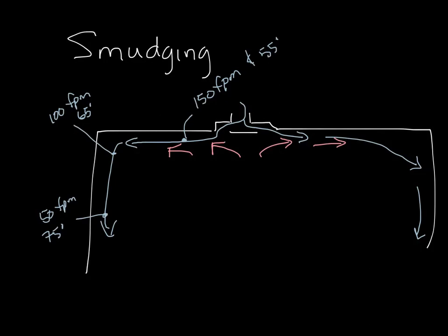The room air is being mixed in with the supply jet to slow the jet down and warm the air up. Since the room air is not filtered, it can carry dust particles to the ceiling, probably not as big as this, but you get the point. And the dirt will stick to the ceiling tiles. Where it is on the tiles depends on the airflow pattern of the diffuser and where the Coanda pocket is. Remember that the Coanda pocket is the low pressure pocket that causes the air leaving the diffuser to be pulled towards the ceiling. So let's draw some diffusers again.